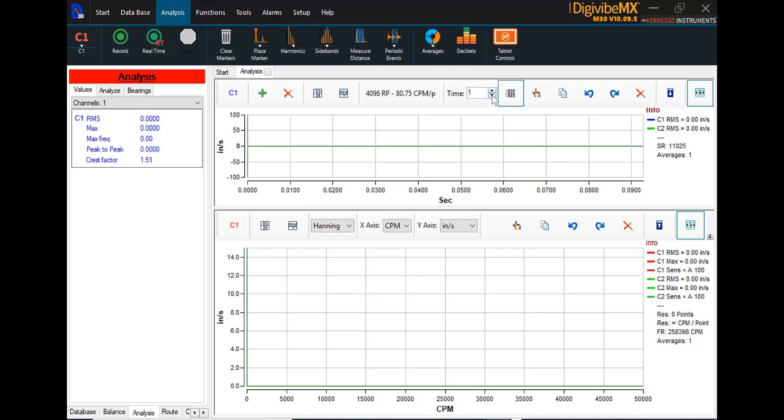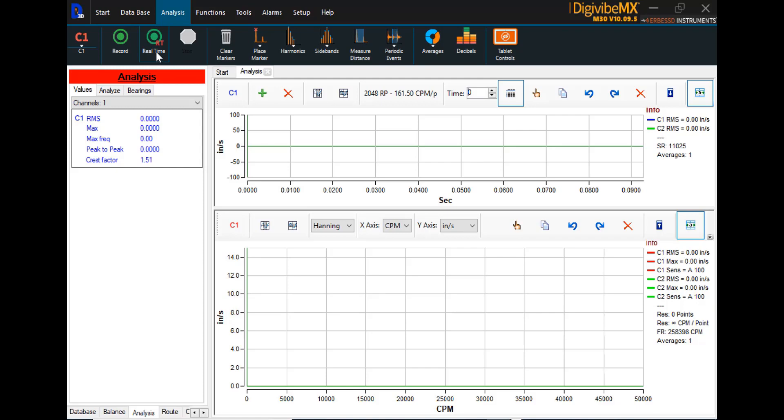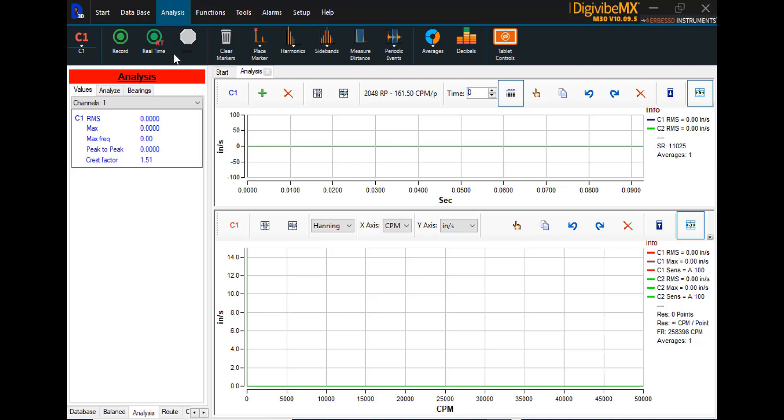Or, if you want to do real-time monitoring, either set the timer to zero and DigiVibe MX will collect continuously until told to stop. Or, you can simply hit the real-time button and DigiVibe MX will collect in real-time again until such time as you tell it to stop. It's important to remember that real-time data collections do not save from beginning to end. The only portion of the collection that will be saved is what is visible in the window while you are recording.